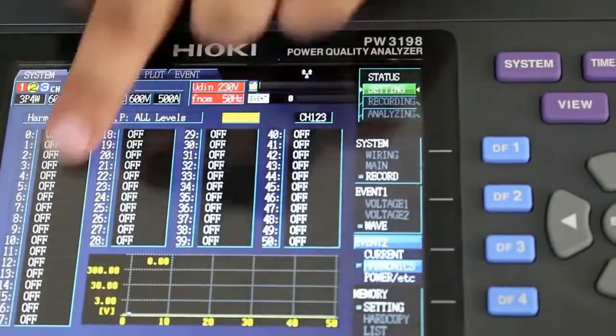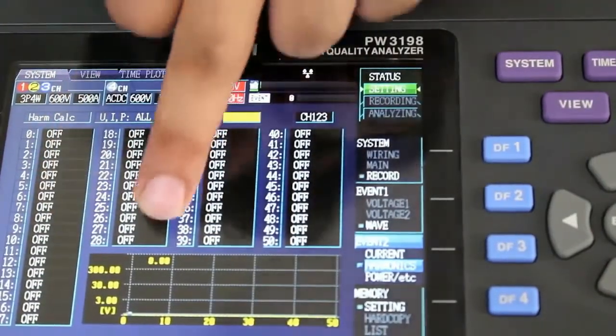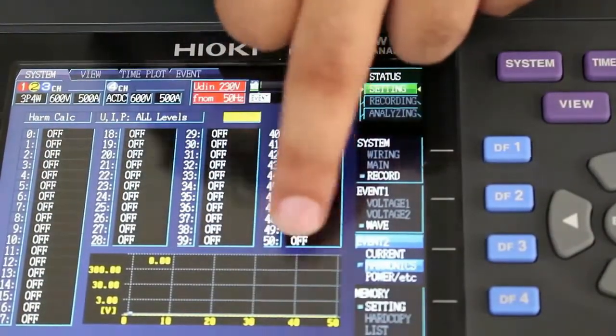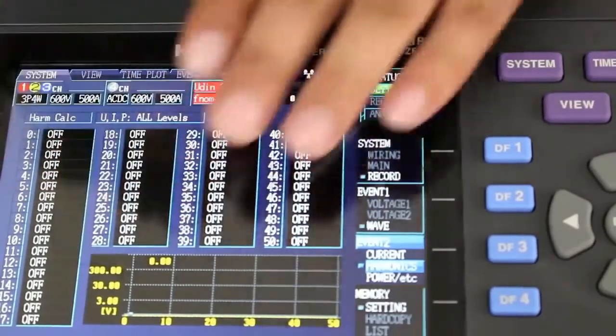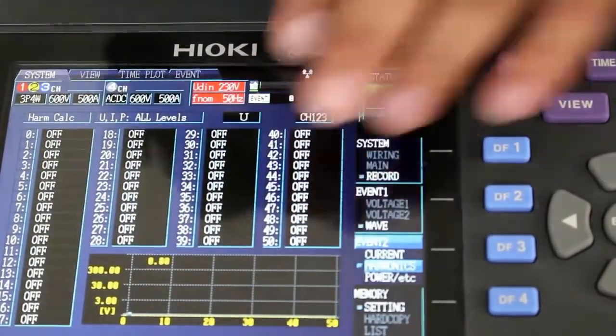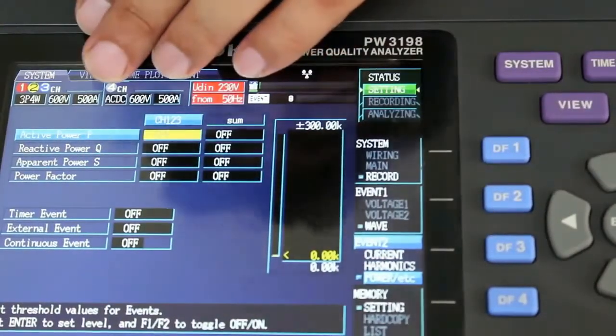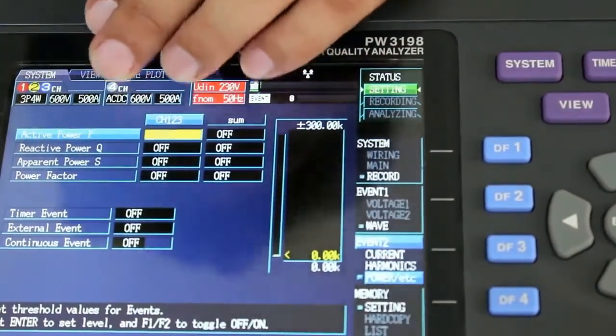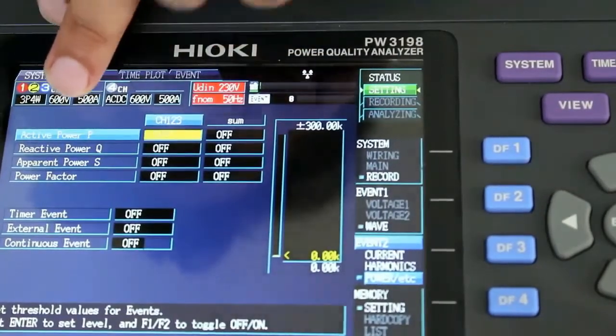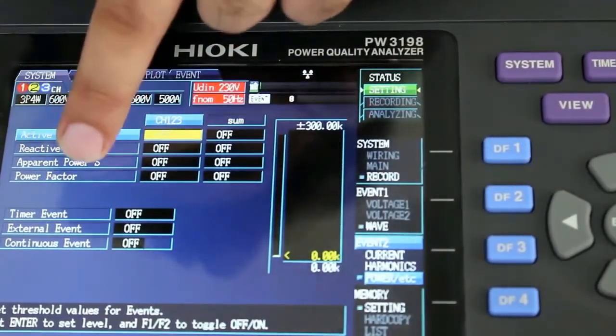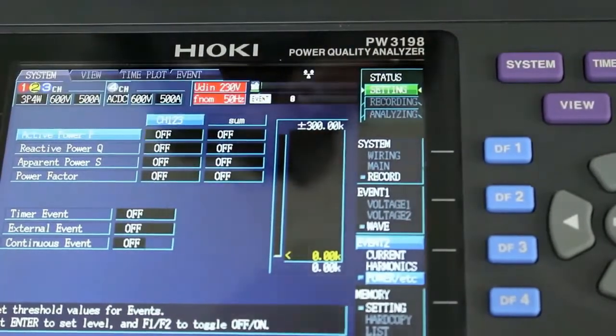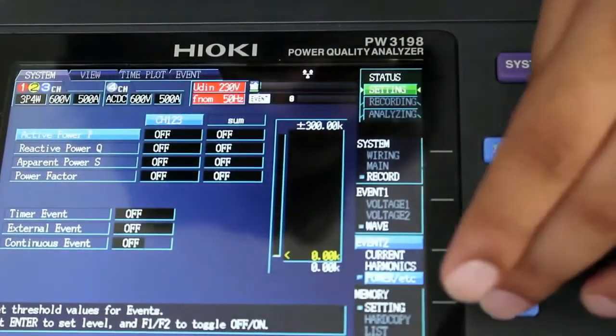Then individually for harmonics, we can also mark the events up to 50th order — this PW3198 instrument can measure up to 50 order of harmonics. We can also mark for power analysis and power parameters, for true, reactive and apparent power, power factor, and time-wise we can calculate the events.